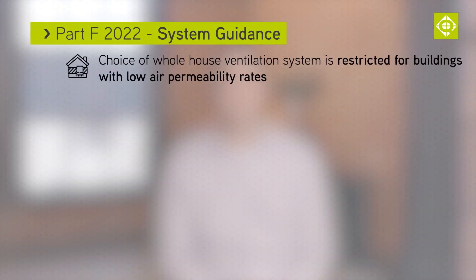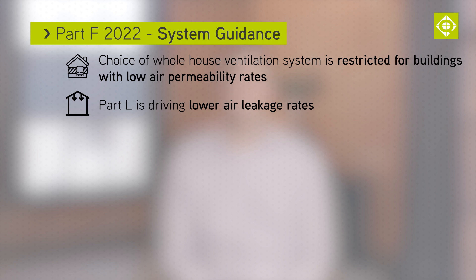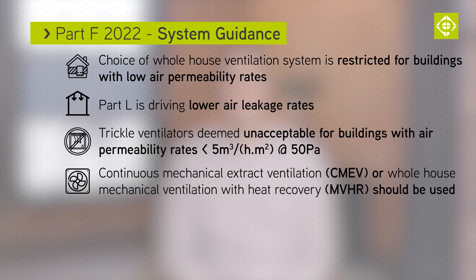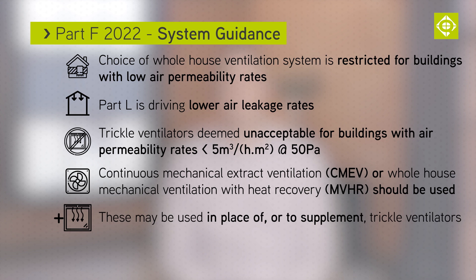For whole house ventilation, the choice of system is restricted for buildings with low air permeability rates. Part L of the building regulations is driving lower air leakage rates. When buildings are designed with air permeability rates less than 5 metres cubed per metre square per hour at 50 pascals, trickle ventilators are not deemed acceptable. In this case, continuous mechanical extract ventilation (CMEV) or whole house mechanical ventilation with heat recovery (MVHR) should be installed in place of or to supplement the trickle ventilators.